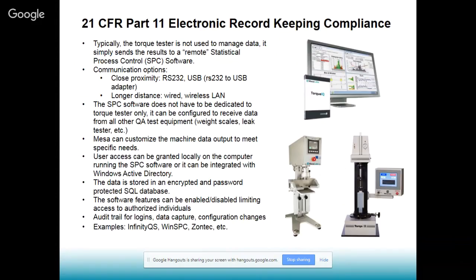With the safety out of the picture, I wanted to take a quick look at the 21 CFR Part 11 electronic record keeping compliance and how we support it. Typically, we recommend that our torque tester is not used for managing data, but instead transfers data to a 21 CFR Part 11 compliant record keeping system. It is just easier to satisfy the requirements on a PC-based system than it is on the PLC.